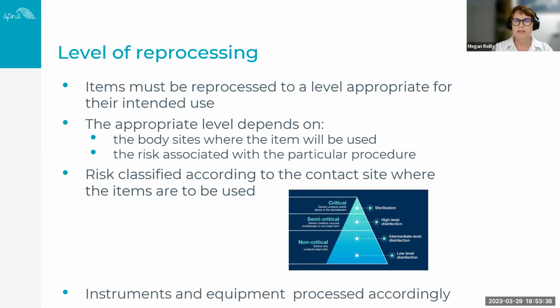So when we talk about reprocessing, we have to determine, or risk assess, to what level an item needs to be reprocessed for the intended use. The appropriate level depends on the body site in which the RMD will be used and the risk associated with the particular procedure. Then we classify that risk according to the contact site where the RMD is to be used, and this is what we refer to as the Spaulding classification system. It categorises medical equipment and devices according to their intended use, and then the subsequent level of reprocessing required to render that RMD safe for use.